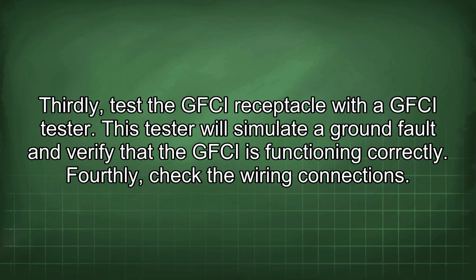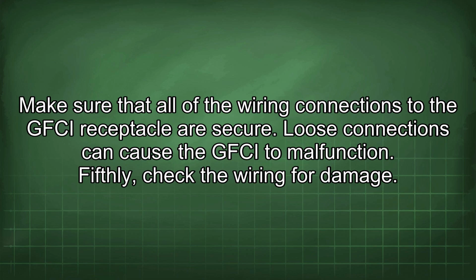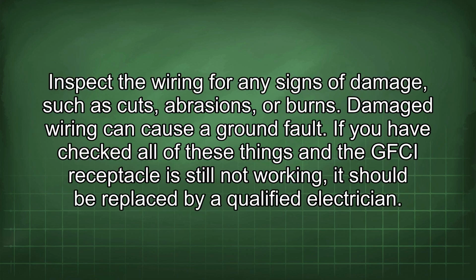Thirdly, test the GFCI receptacle with the GFCI tester. This tester will simulate a ground fault and verify that the GFCI is functioning correctly. Fourthly, check the wiring connections. Make sure that all of the wiring connections to the GFCI receptacle are secure. Loose connections can cause the GFCI to malfunction. Fifthly, check the wiring for damage. Inspect the wiring for any signs of damage such as cuts, abrasions, or burns. Damaged wiring can cause a ground fault.